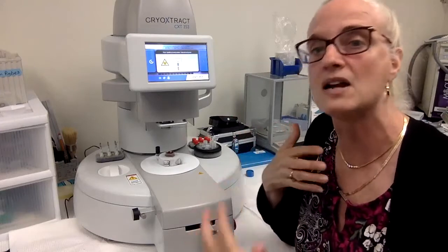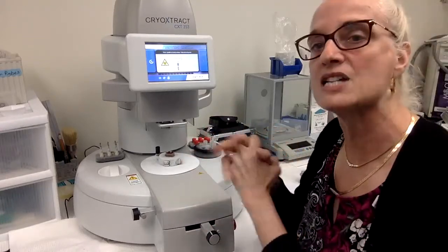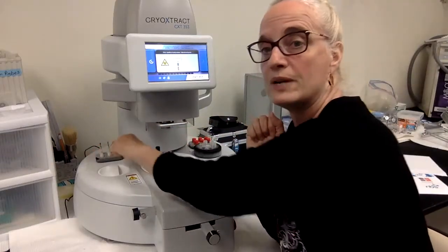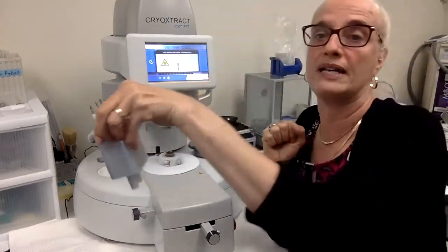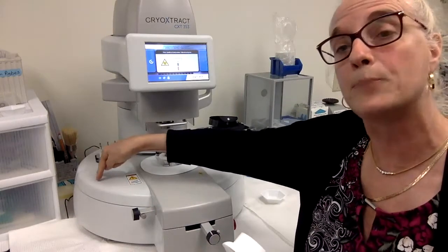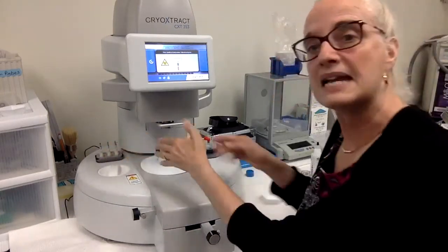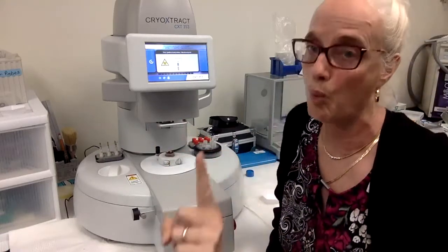It will depend on the temperature in your lab and the percent humidity, but on average it's about 12 minutes. The instrument has removable parts so you can remove the sample nest — this is the sample nest that holds the coring probes. I'm already getting it cold for us. It has a port hole where you can pour your LN2 in. The sample fixture is in the center, and it does process one sample or one tube at a time.